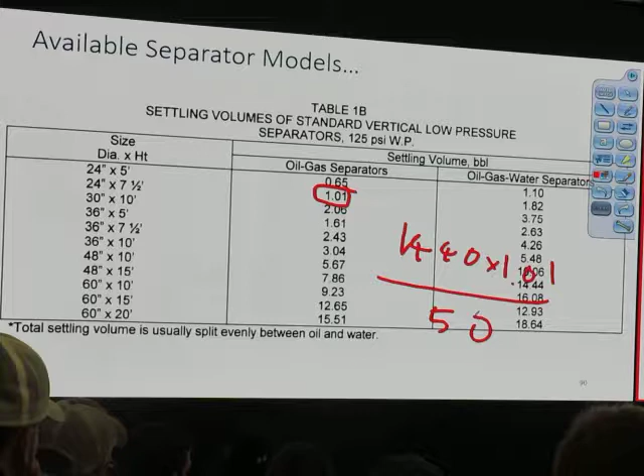Good? Let's say we use the second separator. We use this one, 1.01. I have 1440 multiplied by 1.01 divided by 50 barrel per day. So I have 1440 divided by 50 multiplied by 1.01. I get 29 minutes. So this separator gives me 29 minutes of retention time, for example. You got it?